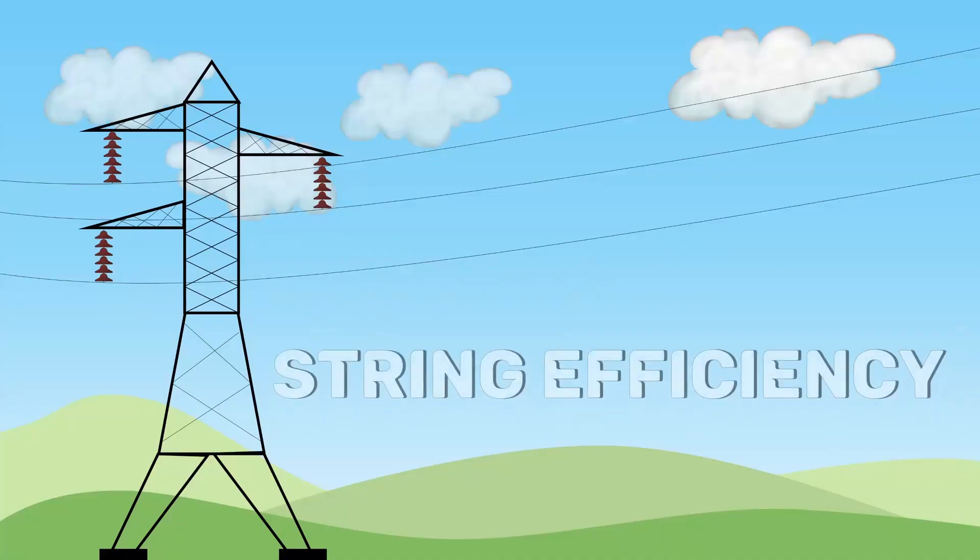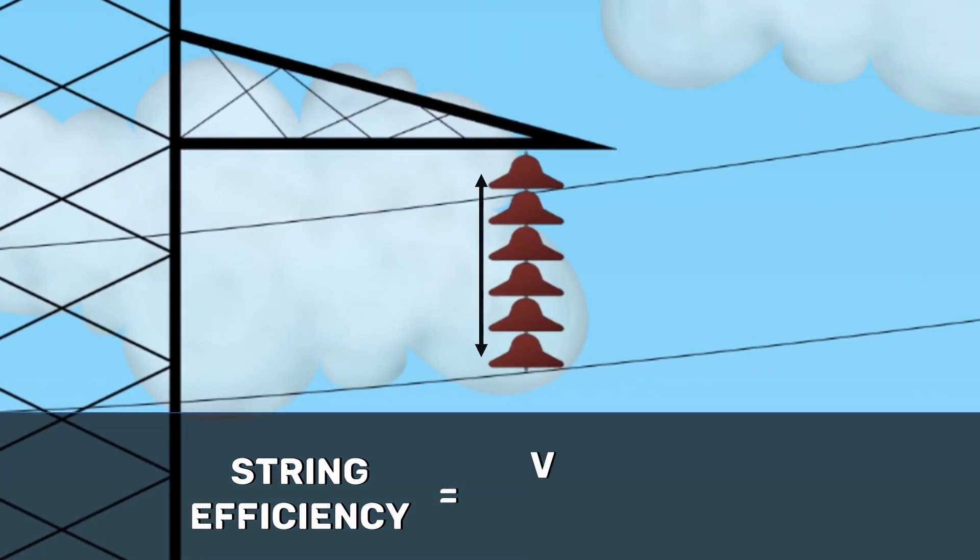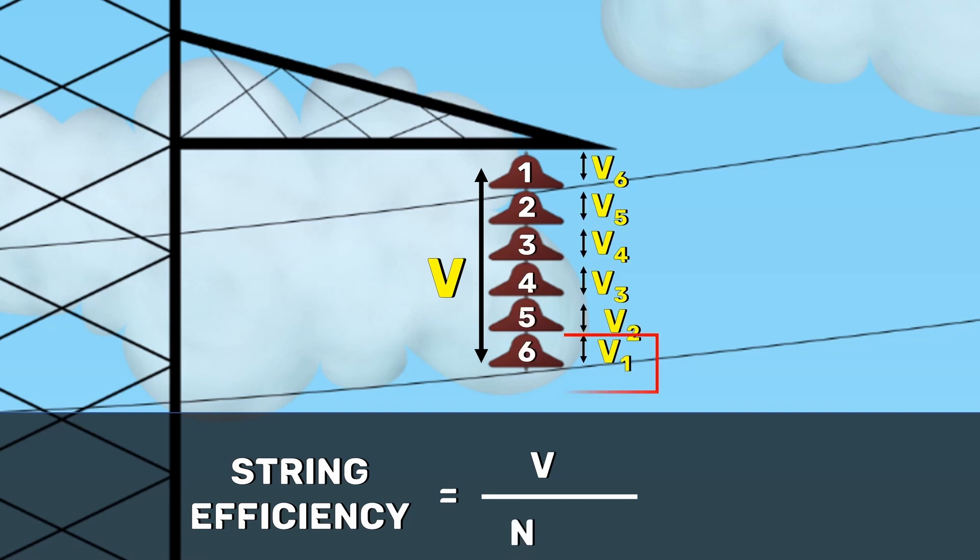In order to avoid this, we need more uniform distribution of voltages. This is usually expressed in terms of string efficiency. It is the ratio of voltage across the whole string to the product of a number of disc and the voltage across the disc nearest to the conductor.